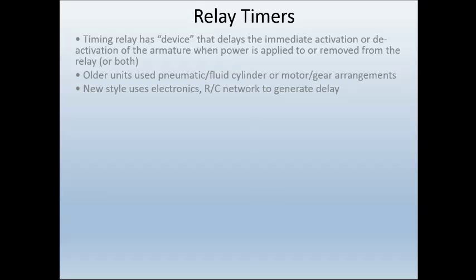Timing relays are a device that delays the immediate activation or deactivation of an armature when power is applied to it or removed from the relay. If we go back to relay logic, we know that we have a relay with a coil. When we energize the coil, it has all these little contacts that will either go closed or go open — to the opposite position than what they are. With timing relays, instead of that action of those contacts happening right away, it actually either delays coming on or coming off.